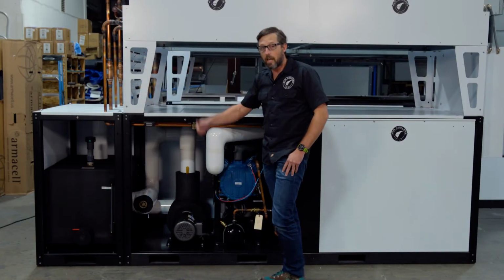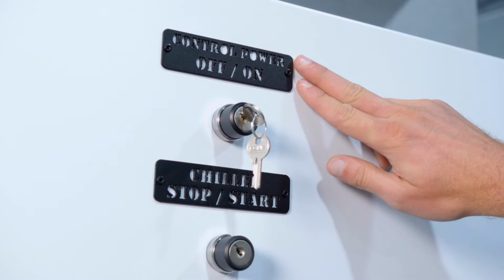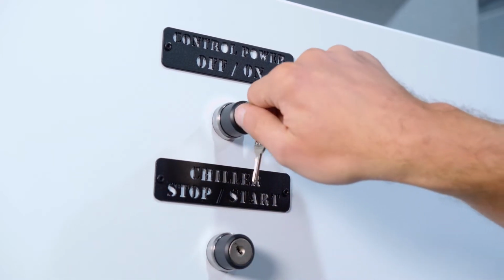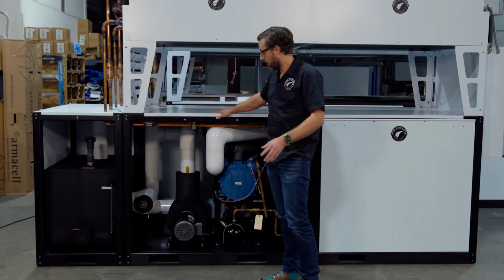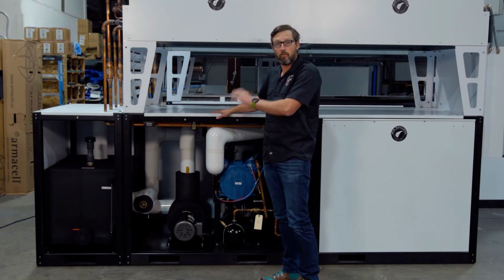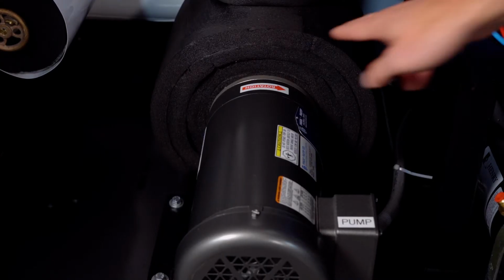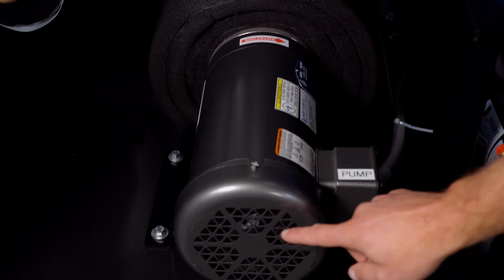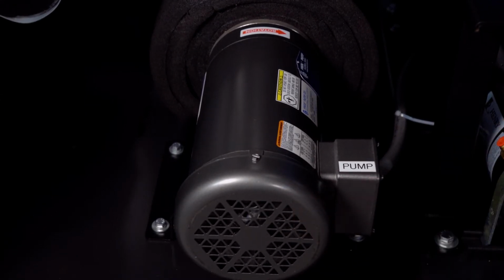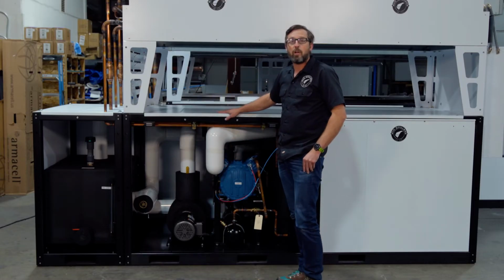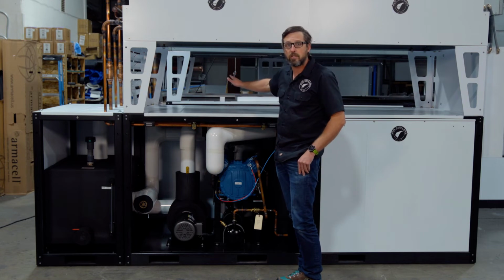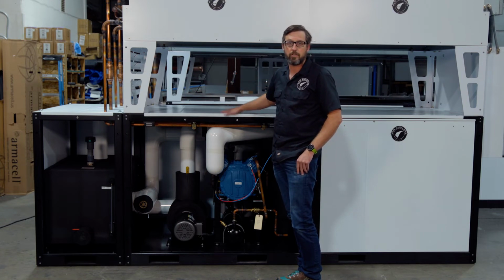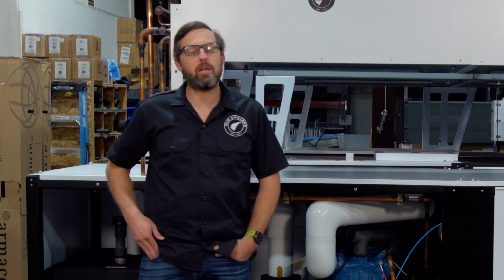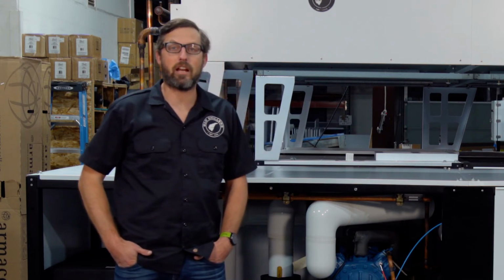Once we do that, we're going to head over to the control panel and we're going to turn on the power to the control system of the unit. That's going to turn the pump on. Whenever we do that, we're going to want to watch this fan on the back and make sure that it matches the rotation that's shown on the pump head here. Once we do that, we're going to open the valve back out to the system and let it flow for about 30 minutes.